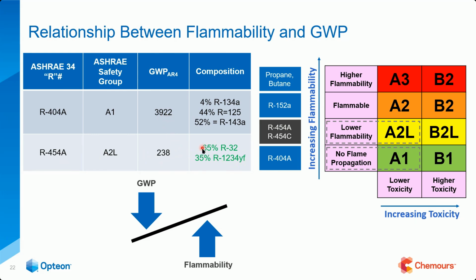What's in it? What are the components? We have 65% R32 and 35% of 1234YF. When it comes to 454A, B, and C, these are the same components in every one of those refrigerants. They just change the ratio depending on what they want the SST to be, your evaporator suction saturation temperature.